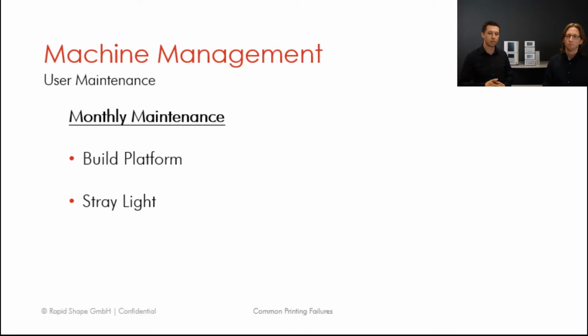Also, there's the monthly maintenance. Monthly, we recommend to check the build platform. Is it parallel? So check the parallelism once a month, or even if you drop it, you can check it directly after the drop. You should especially check it after you dropped it. And you can check the surface of the base plate of the build platform. If it's a little bit shiny, it might be worn out and the part won't stick properly to the platform. The second thing we recommend to check monthly is the stray light. I think Robert also showed you where to find the stray light function and how to check it.